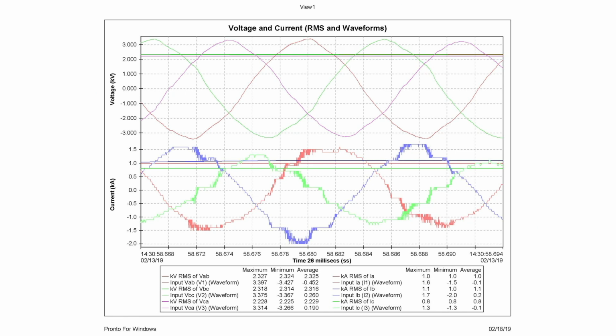So that shows me the noise coming off, which is EMI and RFI generated noise that creates havoc to microprocessors. And in this case, like the Sparks police station, it's creating problems underneath the carport, which created problems to their Bluetooth connected equipment. It generated enough EMI that inside the car, it was creating havoc. And my solution was to put a filter on the inverter to filter out this noise.